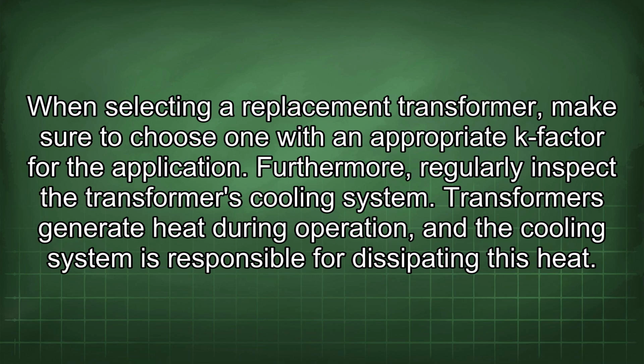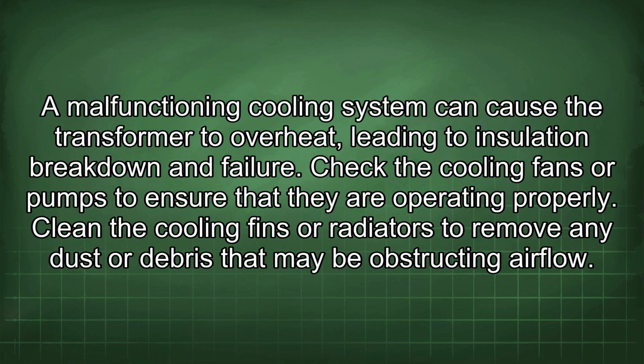Furthermore, regularly inspect the transformer's cooling system. Transformers generate heat during operation, and the cooling system is responsible for dissipating this heat. A malfunctioning cooling system can cause the transformer to overheat, leading to insulation breakdown and failure.